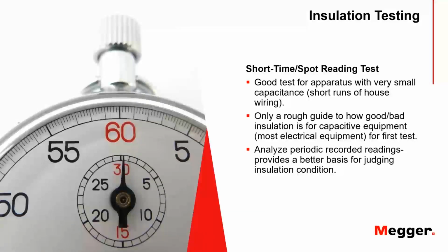So this is a good reading for small equipment because it comes to charging relatively quickly, and so it may give you more information on small equipment. But on large equipment, we're going to look at how our testing procedures take advantage and try to deal with that issue.